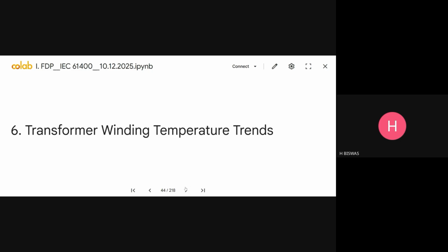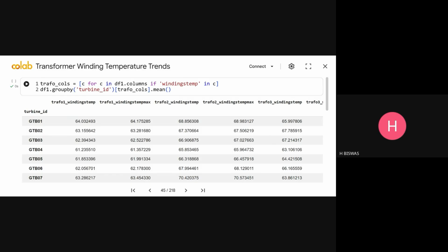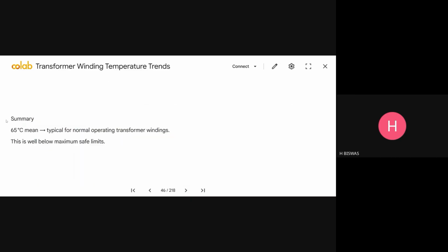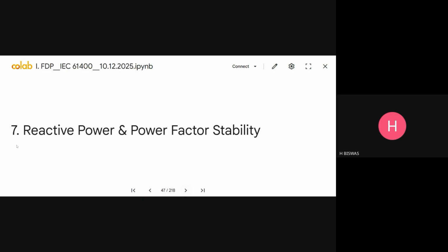Transformer winding temperature trend: we have trafo columns in the SCADA data, giving insight into each particular transformer or winding. A single transformer can have multiple windings, 1, 2, 3 or more for larger turbines. In summary, around 65 degrees is typical for a normal operating transformer winding, well below the max safe limit, indicating the wind turbine is operating more or less healthy.